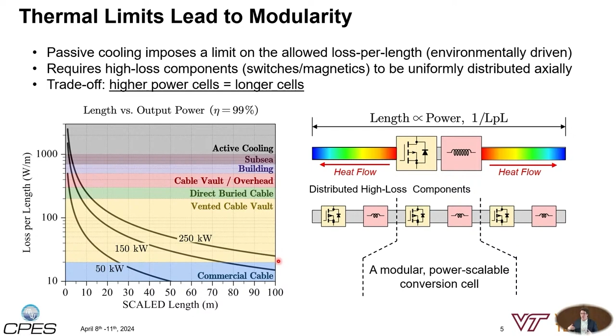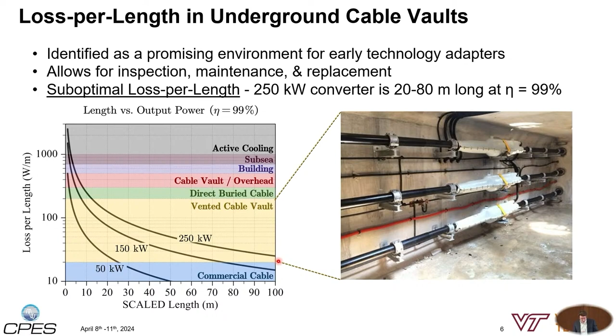Now, in terms of environment, the one we selected for this was an underground cable vault. If you're not familiar with these, it's basically a concrete box under the sidewalk, where medium voltage cable splices are housed so they can be serviced and inspected. We identified this as a good environment for early technology adopters, because it's a pre-existing space, an opportunity for a retrofit. But it is a difficult thermal environment to work with because it's on the lower end of the loss per length spectrum, so we did a little work on this.